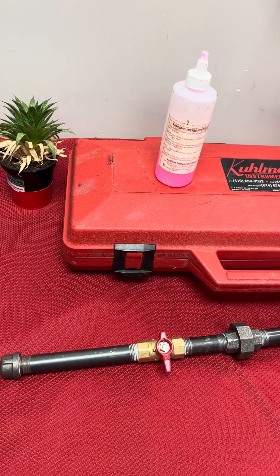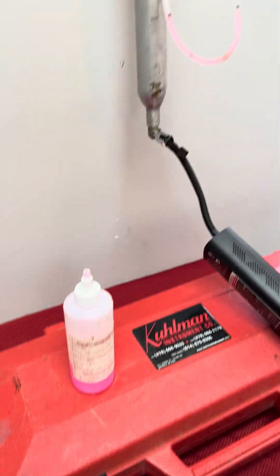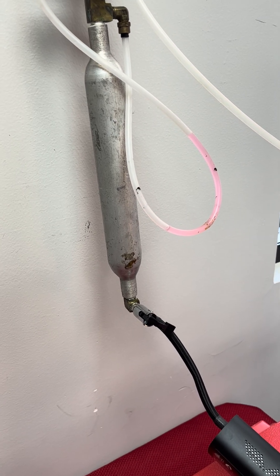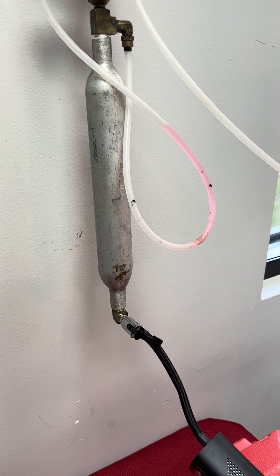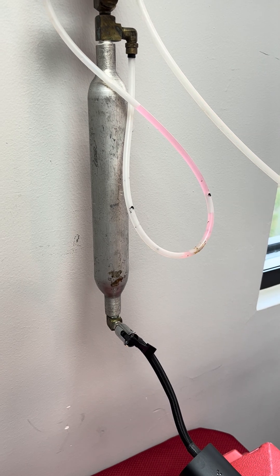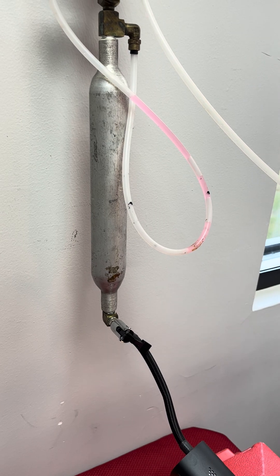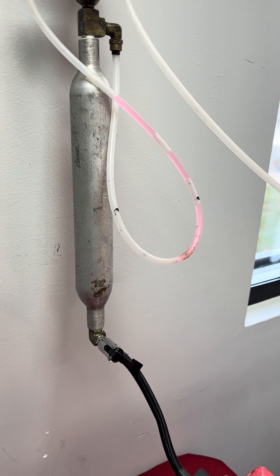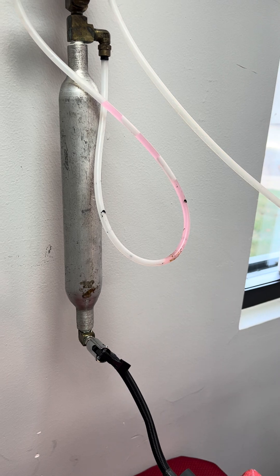What I'm going to do now is open this very gently. As you can see, that caused it to move — the air pressure moving caused it to move. If you see any movement like that, you can see how it's climbing up one side or the other. It may be that severe, it may not be that severe, but if you see any movement past your benchmarks whatsoever, you do have a failed test.